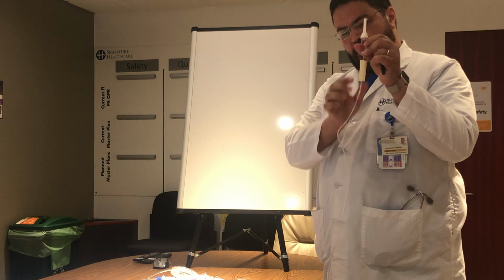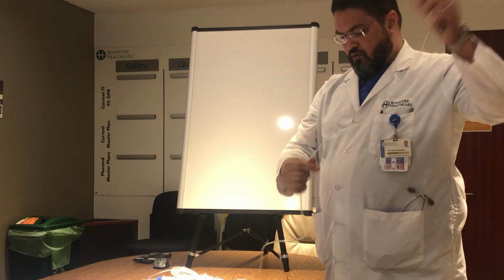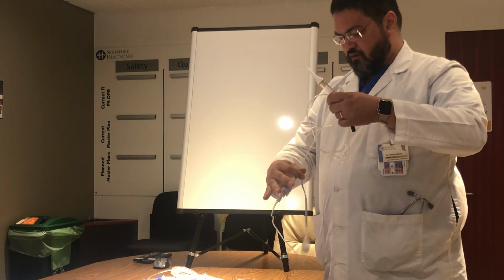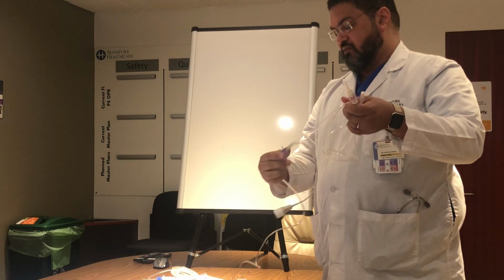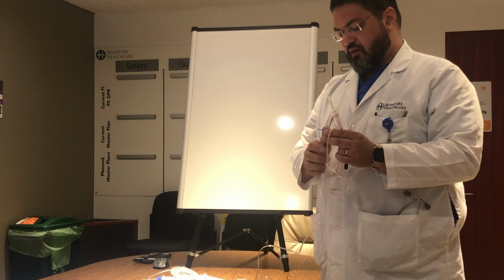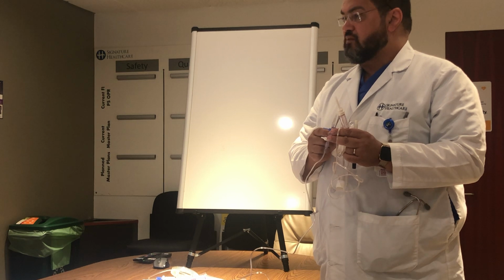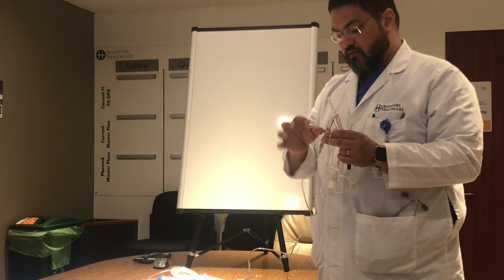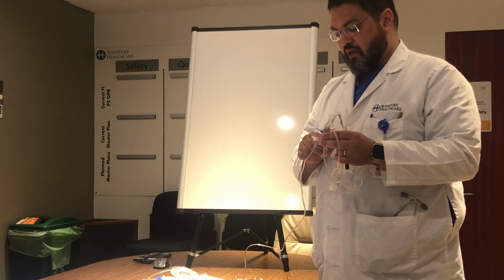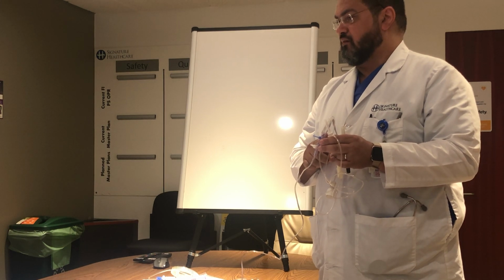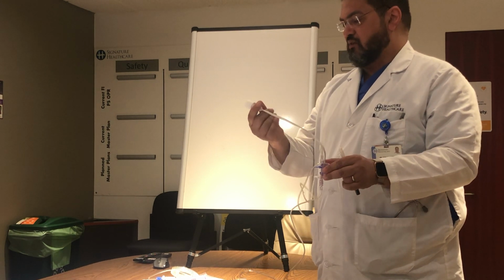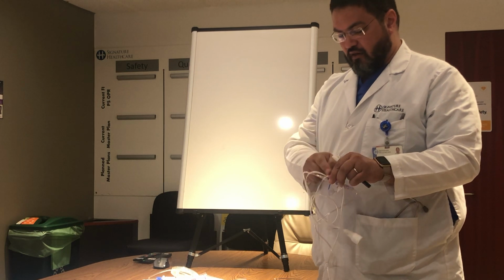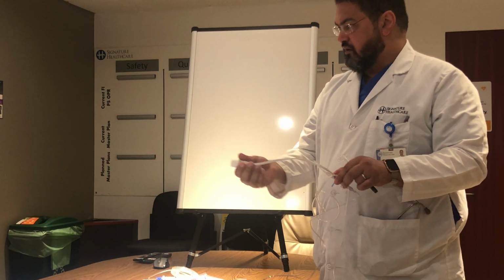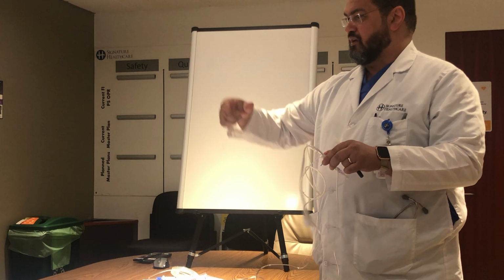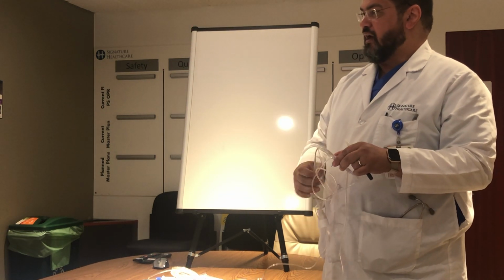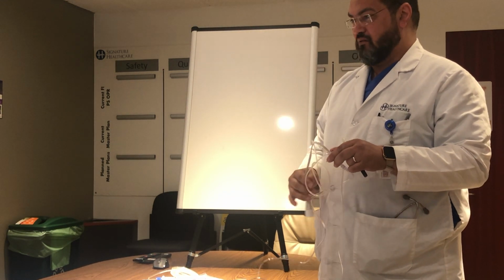Half of it. This has to be open, and it goes like this all the way down here, like a regular IV, and then it meets this part here. This part here is a transducer that measures the pressure. That's the apparatus that measures the pressure, right? And there's a stopcock underneath it, and I'll tell you why we have a stopcock. And then of course it comes directly from the transducer, this cable here, to be connected to the cable that comes from the machine, and that gives us the measurement, right?